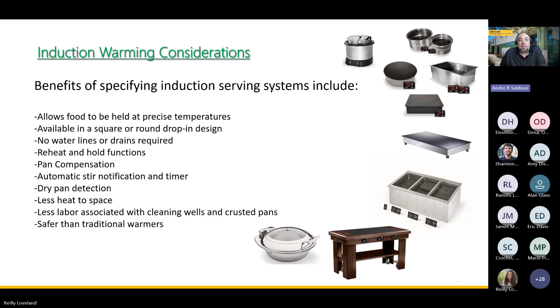We did a study with a large chain that had both dining and drive-through. They were getting inconsistent temps due to water fluctuating, and a lot of cleaning and deliming for scale was needed with wet wells. They moved over to dry wells, about 28 of them, circular and round, with very precise holding temps. Each well had its own holding temp, so no water was needed, resulting in a lot of savings on plumbing and cleaning.